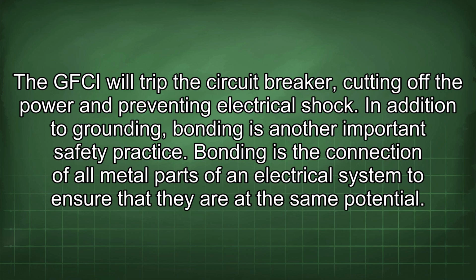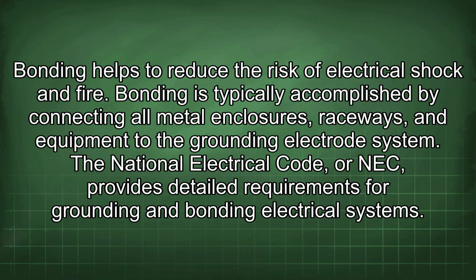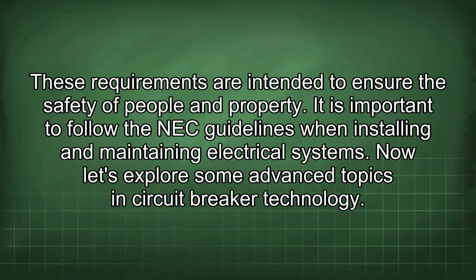In addition to grounding, bonding is another important safety practice. Bonding is the connection of all metal parts of an electrical system to ensure that they are at the same potential. Bonding helps to reduce the risk of electrical shock and fire. Bonding is typically accomplished by connecting all metal enclosures, raceways, and equipment to the grounding electrode system. The National Electrical Code, or NEC, provides detailed requirements for grounding and bonding electrical systems. These requirements are intended to ensure the safety of people and property. It is important to follow the NEC guidelines when installing and maintaining electrical systems.